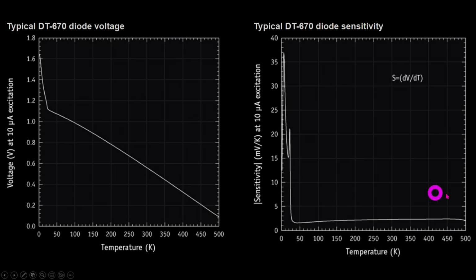But on the right side is a derivative of the same plot. And look, for the majority of that temperature range, you can maintain that 2 millivolt per degree Kelvin, which is very characteristic of a silicon p-n junction. So if you calibrate this, you can get extremely accurate readings. You can see it begins to change a little bit down here, but we really want to be able to bring it all the way down to here in order to make the measurement we want. So what we really want is to pick any silicon diode, as long as it's reasonably well hermetically sealed, that matches the forward bias voltage at the excitation current of our instrument, and then we can fool it and let it read that measurement instead, and it's going to be accurate enough for our purposes.